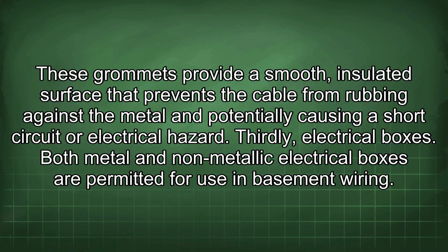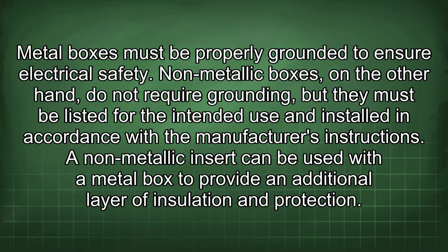Thirdly, electrical boxes. Both metal and non-metallic electrical boxes are permitted for use in basement wiring. Metal boxes must be properly grounded to ensure electrical safety. Non-metallic boxes, on the other hand, do not require grounding, but they must be listed for the intended use and installed in accordance with the manufacturer's instructions. A non-metallic insert can be used with a metal box to provide an additional layer of insulation and protection.